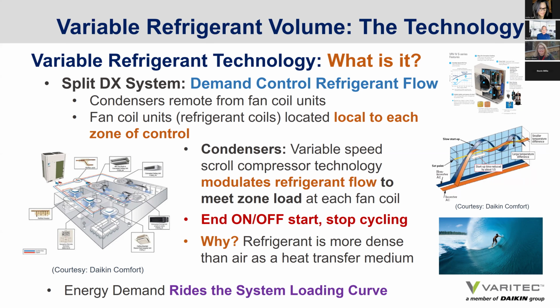And variable refrigerant technology uses variable speed scroll compressor technology to modulate refrigerant flow throughout the building depending on demand. By modulating refrigerant flow dependent on demand, you end the energy-consuming process of on, off, start, stop cycling. Many of you in your homes who have air conditioners are fully aware, certainly during the summer, when your AC unit fan kicks on and off, and your compressors turn on and off. Well, that surge of energy necessary to overcome the inertia of a stop mode is significant, and it's very inefficient. And we want to do this locally at each zone, as I mentioned earlier, because refrigerant is a more dense heat transfer medium than air.